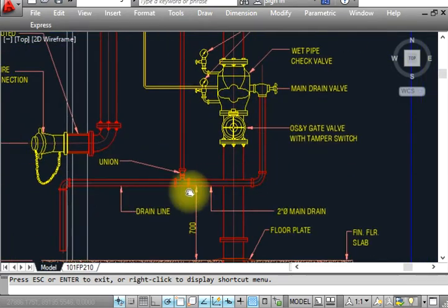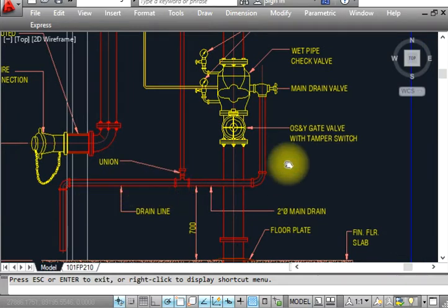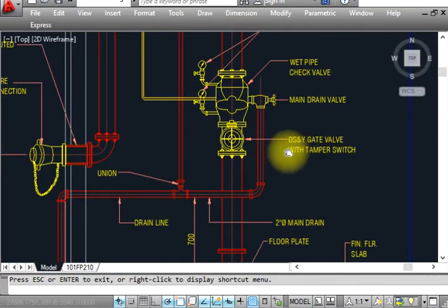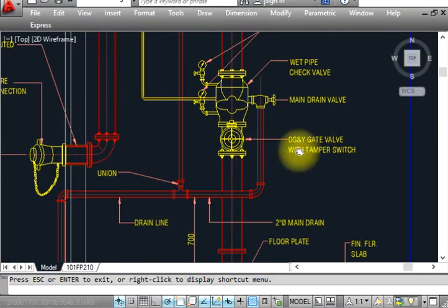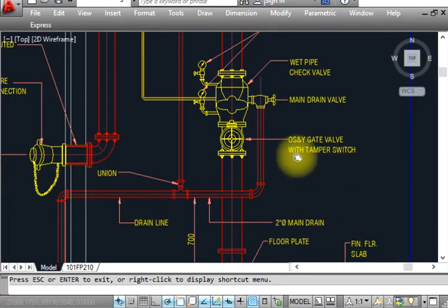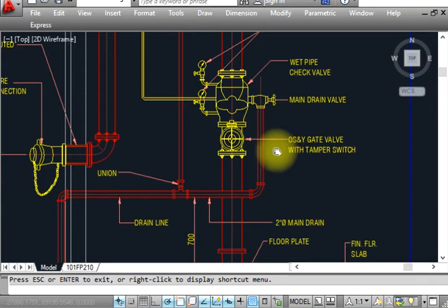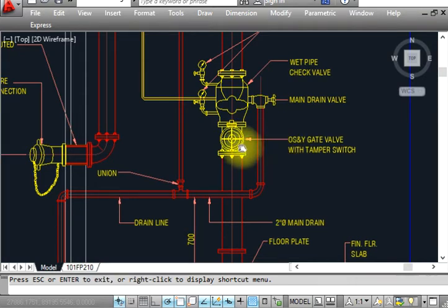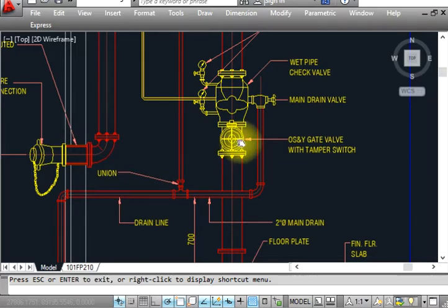This is the same gate connected here and going here. This is an OS&Y gate valve with a tamper switch. Basically, I told you this is the function for the gate valve, the OS&Y valve. In an OS&Y valve, we can see visually by sight if it's open or closed.